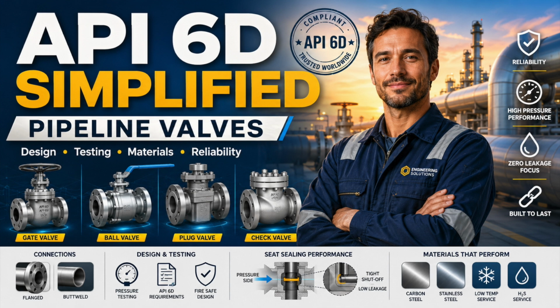A pipeline valve can be perfectly compliant, correctly tagged, successfully pressure tested, and still be wrong for the service. That is the uncomfortable truth. You can buy the right size, the right pressure class, and the right valve type, yet still end up with the wrong sealing direction, the wrong seat philosophy, the wrong bore, the wrong cavity pressure behavior, the wrong actuator sizing, or the wrong material system.